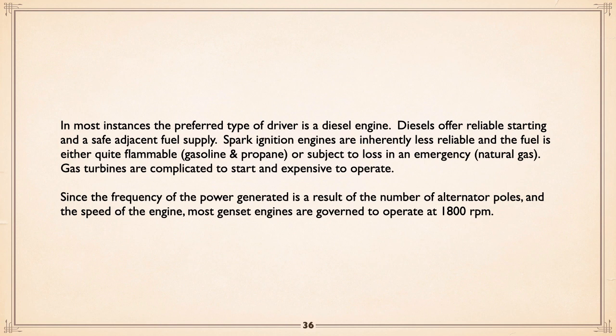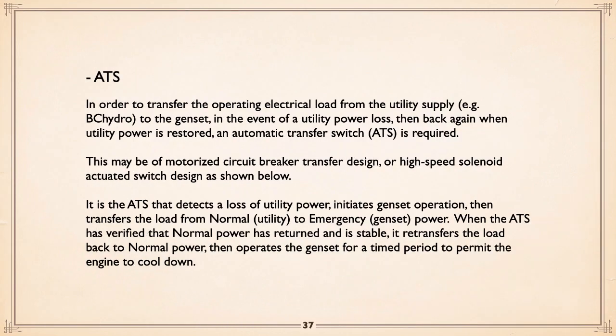Now, since the frequency of the power generated is a result of the number of alternator poles and the speed of the engine, most genset engines are governed to operate at 1800 RPM. There's the occasional, at one time, 3600 RPM, very small diesels. And if you get into larger sizes, really big stuff, then you're down to 1200 RPM. And maybe even lower. But basically, the vast majority, 1800 RPM. So there's your fundamentals of a generator. We'll get into how they're packaged as a genset in a bit here. Automatic transfer switch.